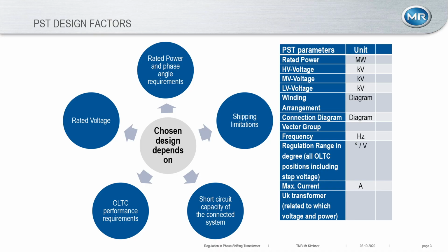So first of all, when we start thinking about phase shifting transformers, then we would, of course, look at rated power, and this is not different to any other transformer. The next thing would be the phase angle. So we are not talking about percentage of regulation range. Here we're talking about an angle in degrees and how many steps we would need to realize a certain angle. So this would be different to normal transformers. Then, of course, rated voltage of the system line is important for the design.